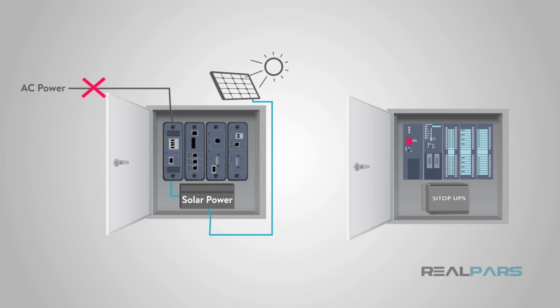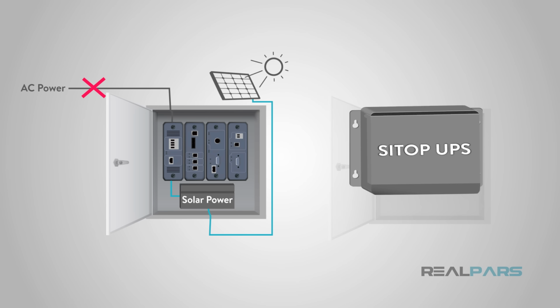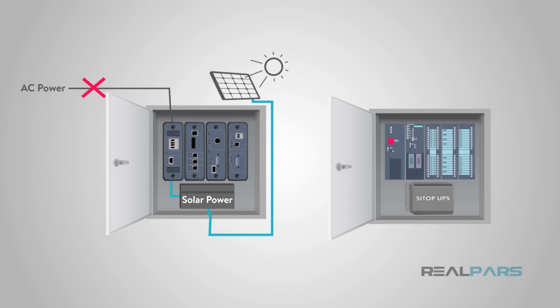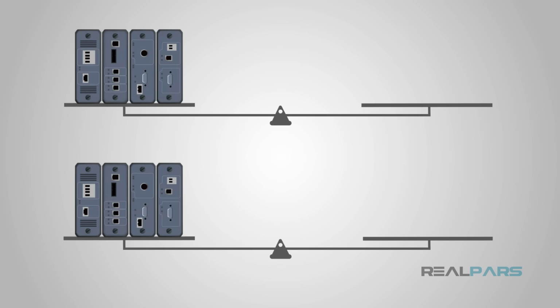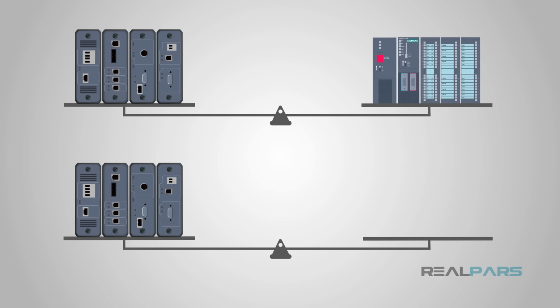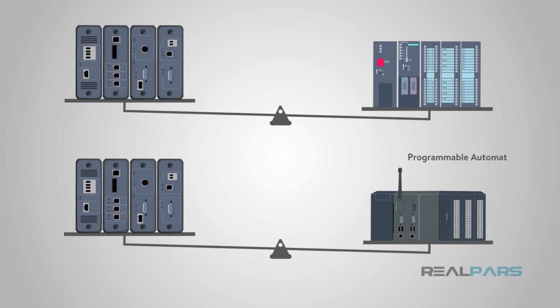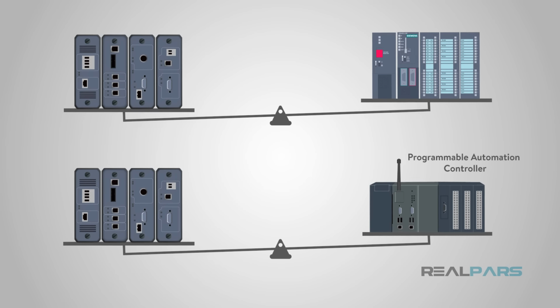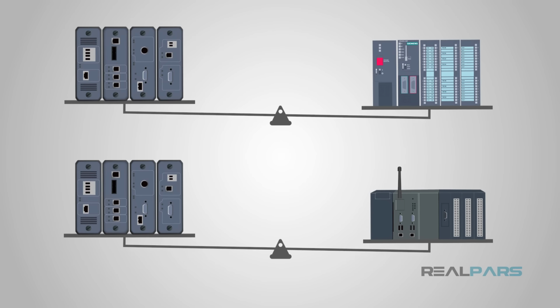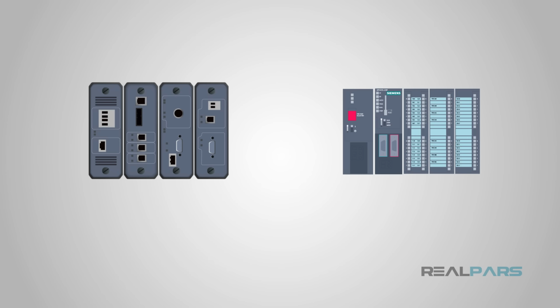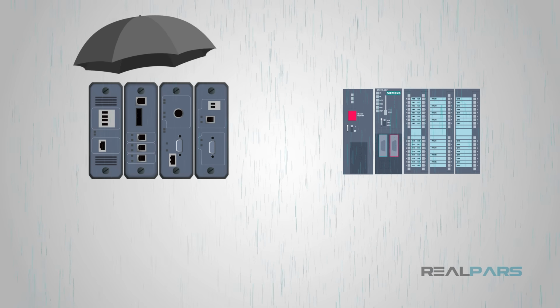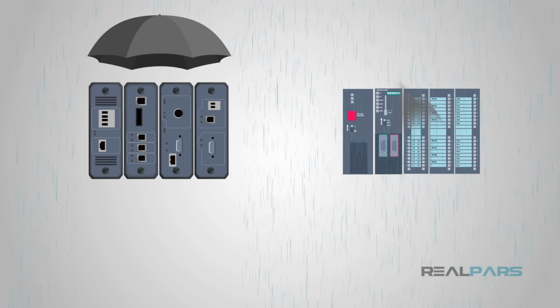Of course, PLCs can have a UPS backup, which adds the same benefit, but the charging circuit is a definite plus. The advantages that were described here can easily be mitigated with the new PLC and PAC, Programmable Automation Controller Systems. Just about every category of advantage can be found in other options. The biggest advantage is the environmental tolerances. Those are hard to compete with.